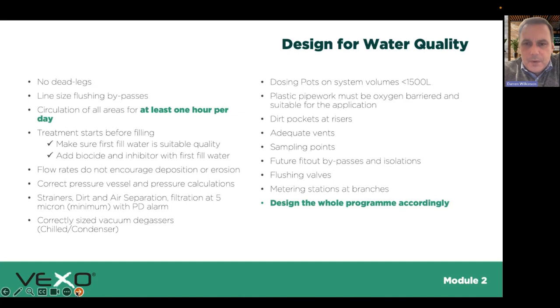Plenty of vents, sampling points, and if you're working on a shell and core, you do have a fit out. Can have a lot of fit outs. Make sure you've got the right fit out bypasses and isolation. So, i.e., if a tenant comes onto that floor, you can isolate the floor, but open the bypass. Make sure there's a bypass installed, and certainly as close to the riser as you can. Think about flushing valves for the installers on the fit outs as well as the main system, and making sure there's metering stations at the various branches to prove the flushing velocities achieved, basically.